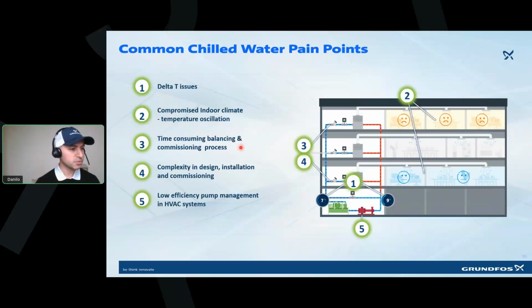Another thing is the time consuming balancing and commissioning process, right? How are you going to balance all those valves, which is what's going to deliver the comfort to your guests, or if some people are struggling with temperature control. On top of that, you could have complexity in design, installation, commissioning. I'd say three and four go hand in hand. And last, not least, low efficiency pump management for your primary pump. That's exactly what we spoke about in the past, right?